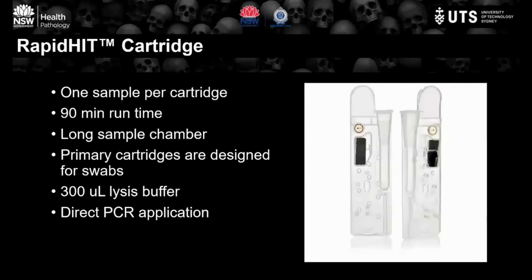The RapidHit ID system uses a primary cartridge where the sample is added. One cartridge holds and tests one sample, taking approximately 90 minutes. The sample chamber is long and narrow because it's designed for a swab, where the biological material is at the bottom. 300 microlitres of lysis buffer is added and then removed from the sample chamber before proceeding for direct PCR.